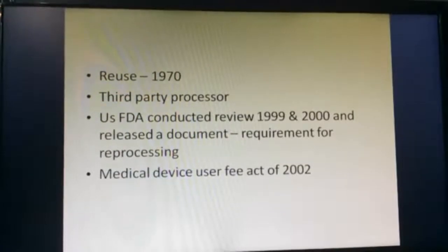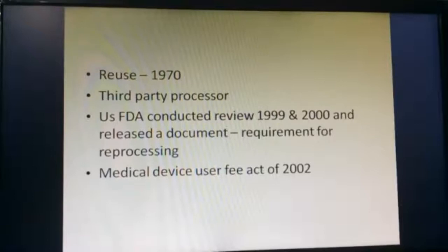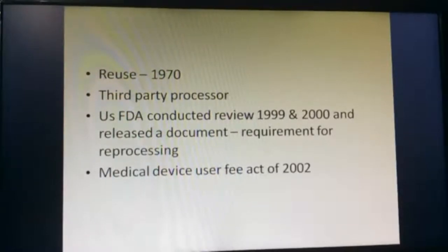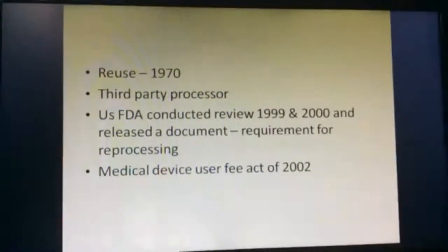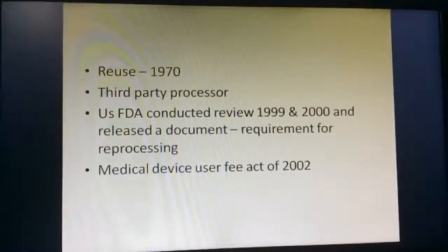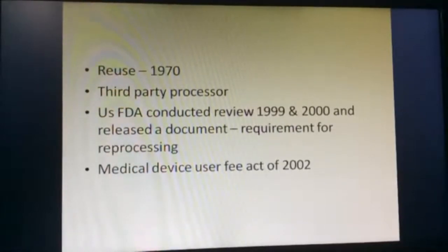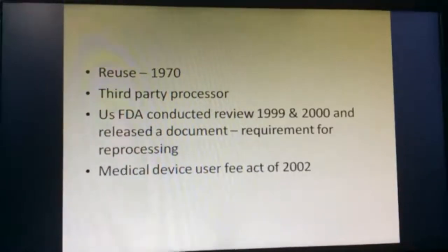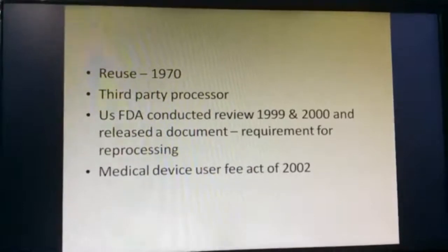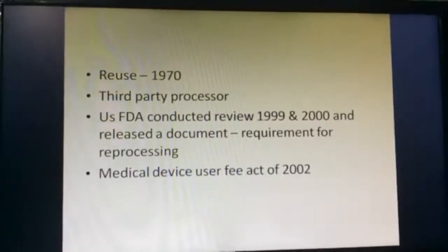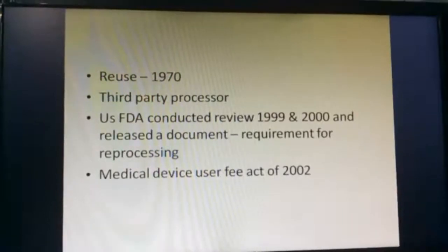started way back in 1970 when ethylene oxide, ETO, sterilization came into the picture. The US started the first reuse processing by hiring a third-party reprocessor. The US FDA conducted a review in 1999 and 2000 and released a document, a guideline, with the requirements for reprocessing. And then they amended the act, the Medical Device User Fee Act of 2002. And they've clearly given guidelines that the reprocessor should be a third-party processor and should follow all the terms and conditions of the manufacturer.